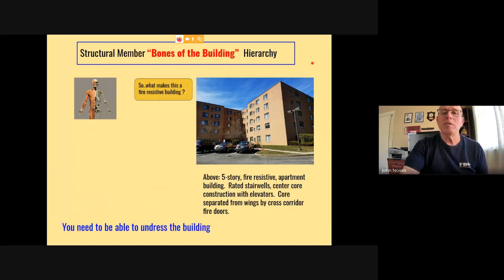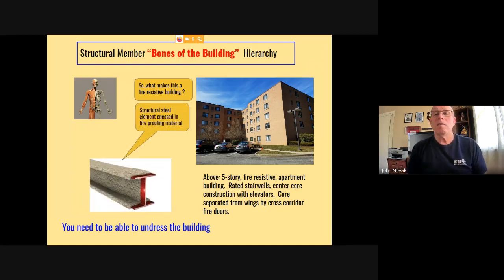So what makes this building a fire resistant building? Just keep in mind the last part we did was non-combustible. That was a non-combustible building, but this is a fire-resistant building. So what makes this fire-resistant? The biggest component is the bones of the building, the structural members; they are encased in some type of fire-resistant material. In the illustration, we have an I-beam that has sprayed on fireproofing attached to it. That's going to give it protection against direct flame contact for a rated number of hours.